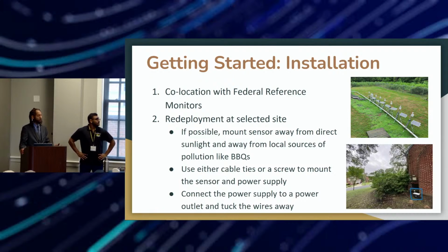Specifically with the PurpleAirs, they're pretty good, but what I try to avoid with the installation and what's recommended is to keep them away from HVAC sources. So you wouldn't want to install it next to your heater or your AC unit. Another place that I wouldn't like to put them would be, say for instance, if I was installing at a church. Most churches have a kitchen, for after service. So you wouldn't want to put it by that kitchen exhaust because it would throw off the readings.